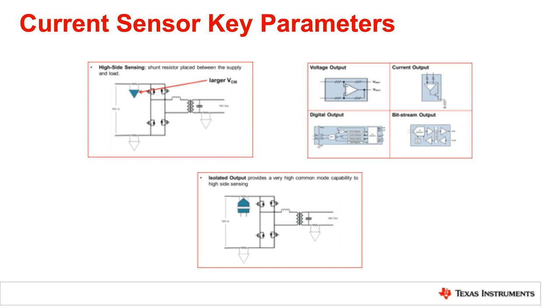The preferred solution is actually to use a bit stream amplifier. What this device will do is actually isolate the output of a delta sigma modulator. This isolated output is going to provide a very high common mode capability into your high side sensing application.